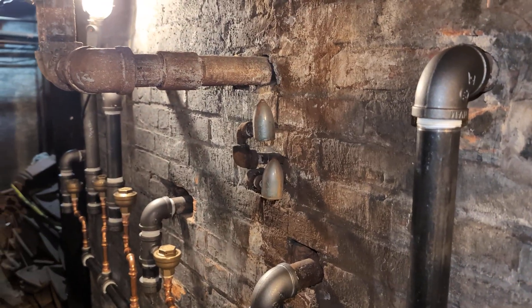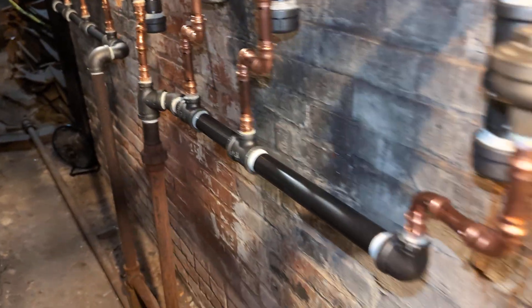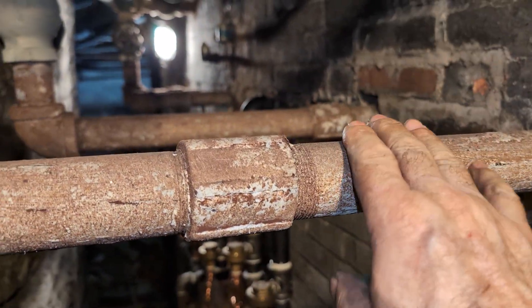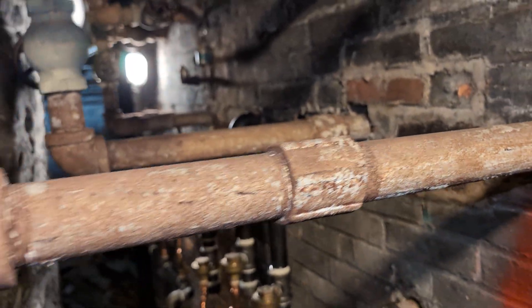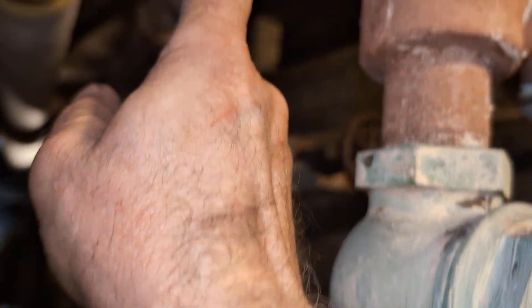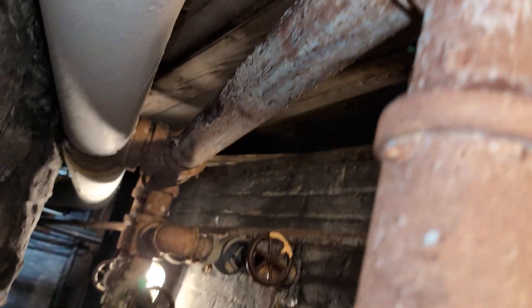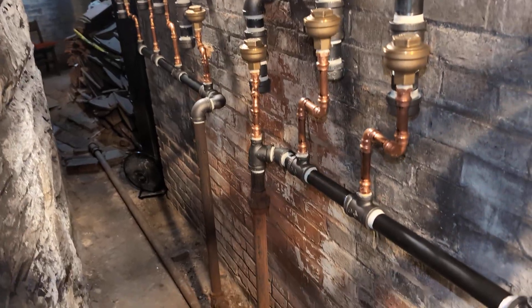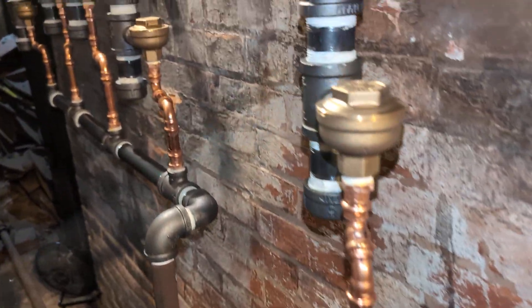We hope to save a little time by putting this back online. We've advised the customer to insulate these pipes — this one is about an inch to inch and a half, and that one is two inch, and that one is two and a half inch — and that will help keep this area cooler and not waste so much steam.